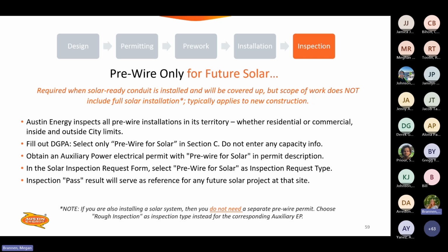Now, the other option that can be confusing for folks is the pre-wire only permit and inspection. A pre-wire permit is essentially a rough inspection, but with no solar capacity or energy storage capacity. So basically, if you want to get a building solar ready and make sure all the conduit is in the walls and everything's covered up as needed, that's when you would call for that pre-wire inspection. Austin Energy inspects all pre-wire installs in its territory. We will note this on your permit as well, so you'll have a record of it into the future if this customer decides to go solar 10 years down the line. You would still obtain the aux power permit with the option pre-wire for solar in the permit description as well as the DG type. And then an inspection pass result will serve as reference for any future solar at that site.